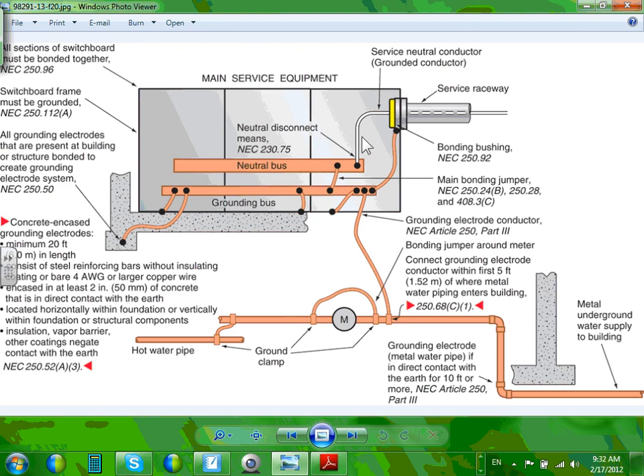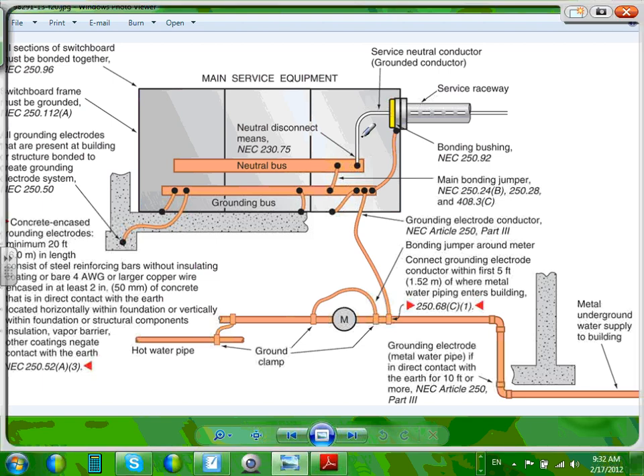The only thing I want to say at this time about bonding and grounding is you have to create a grounding electrode conductor at the service. You have to bond the neutral to the grounding electrode conductor, right? The neutral. And the calculation is coming. So here's my neutral, I'm going to bond. Can you guys see that neutral is bonded to the grounding bar, and the grounding bar is bonded to the water. It's bonding to the concrete.